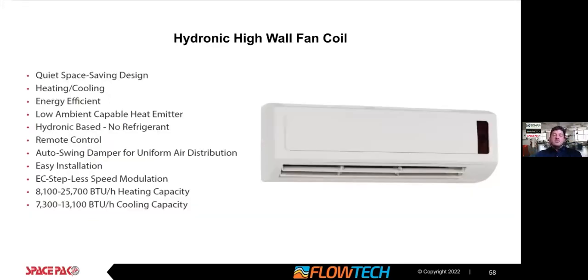Moving on to our hydronic high wall fan coil. Albert mentioned this too, and these are great options. I can't tell you how many times I have designs that come in and I see a SpacePak specified for heating, whether it's radiant or thin wall units, and then a whole separate system for cooling: a mini split system. They've got the outdoor unit, the line sets, the high walls. And then we show them, hey, you can do the same thing with what looks like a high wall from a mini split and eliminate that outdoor unit. This takes that heated or cooled energy and distributes it through different areas in the house where these units are placed. It's remote control, but there are some different strategies on simplifying the control of these units, and they do a really good job of providing that cooling and heating.